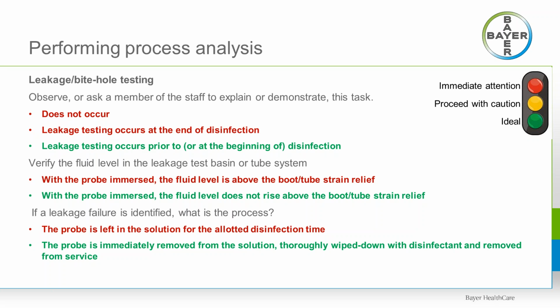It's also important how much of the probe is immersed in the test fluid. Most manufacturers state that the probe should not be immersed higher than the last number that is stamped on the insertion tube. And it's really because that rubber boot that leads to the control housing is not waterproof. One final item is to identify what happens if the leakage test fails. If the test fails, the probe again should be removed from the liquid immediately, thoroughly wiped down with a disinfectant wipe, and removed from service.